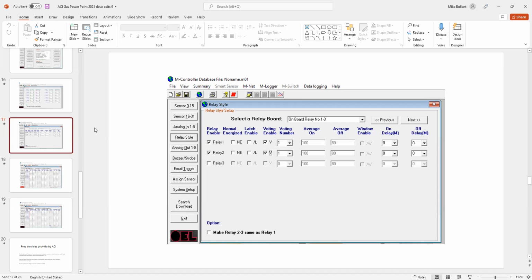And let's just say that you've got CO, NO2, or even hydrogen or oxygen on the same loop. The voting will enable the relays that are on there. If any one of those relays go off, even though it's not CO or NO2, it'll send the alert back to the relay.